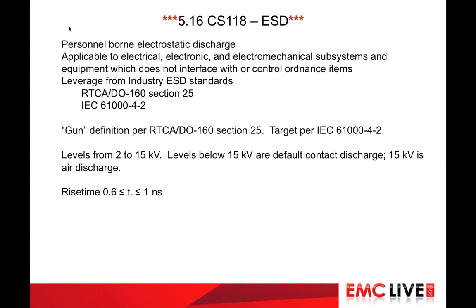The test method and equipment is leveraged from industry ESD standards, RTCA DO 160, Section 25, and IEC 61000-4-2. The waveform definition is from RTCA DO 160, Section 25. The target is from IEC 61000-4-2. Once again, if a test facility has a capability to perform these tests, no new equipment is necessary. Levels are from 2 kV to 15 kV. Levels below 15 kV are default contact discharge. 15 kV is air discharge. 8 kV is the ordinary requirement. 15 kV has to be specified by the procuring activity. Rise times are about 1 nanosecond, requiring an oscilloscope with single event bandwidth near 1 gigahertz.